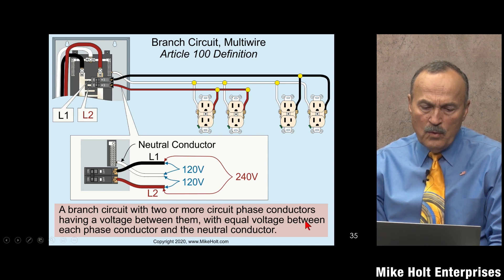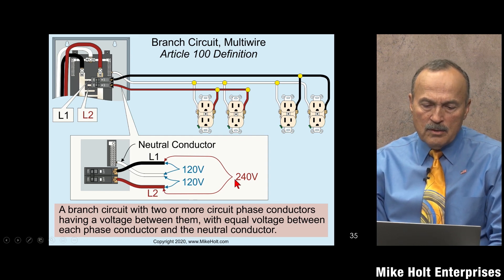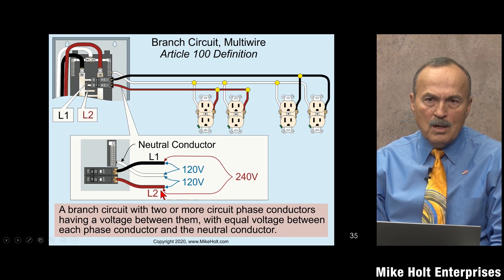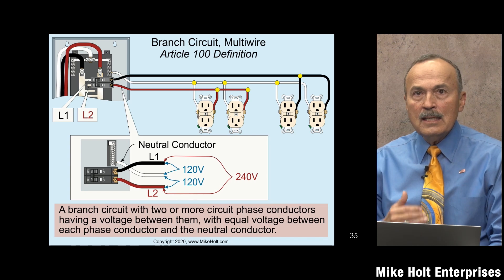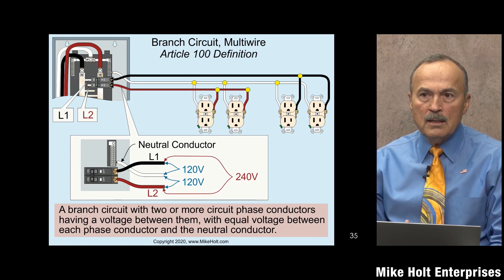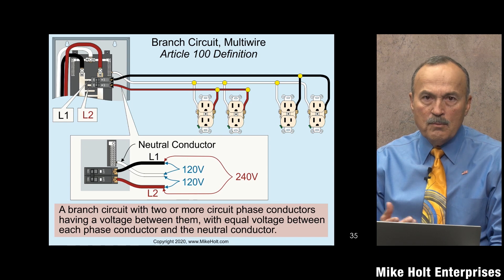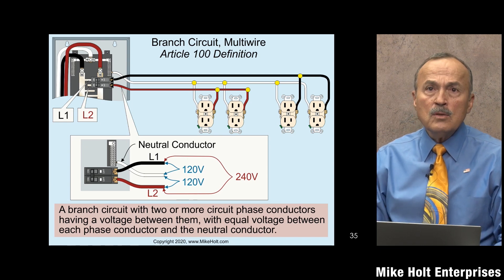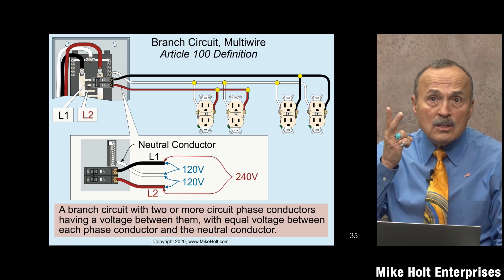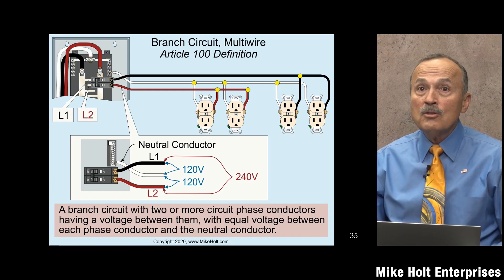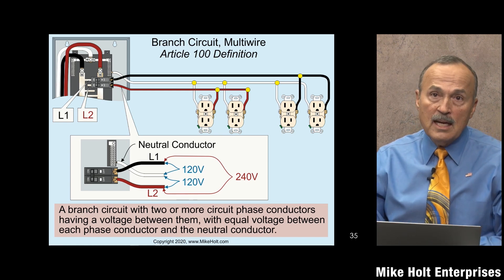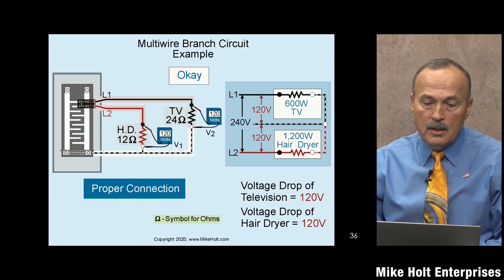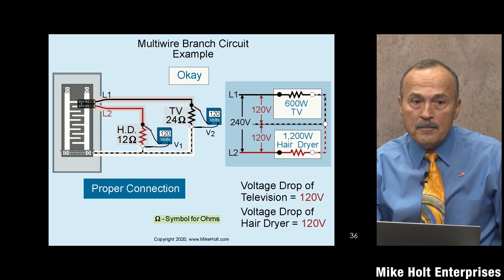The voltage between the phase conductors is 240 volts, with equal voltage between each phase conductor. In a three-phase system — A to B, B to C, A to C — all voltages are equal, like a wye system. So a multi-wire branch circuit lets you use two hots and one neutral, saving a wire instead of running a separate hot and neutral for each circuit.